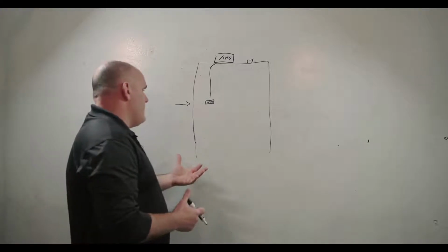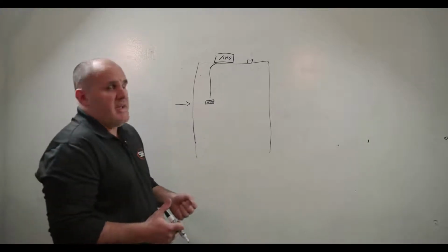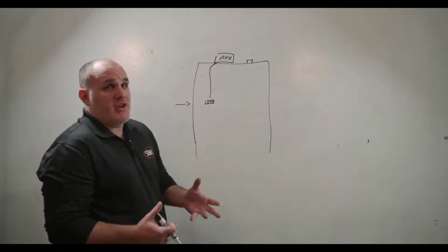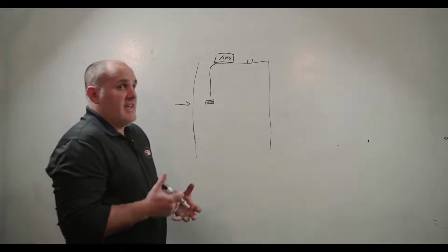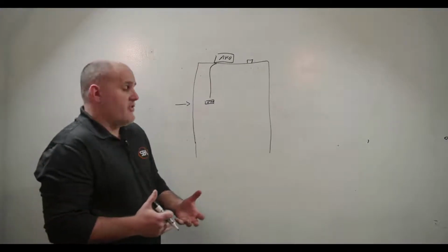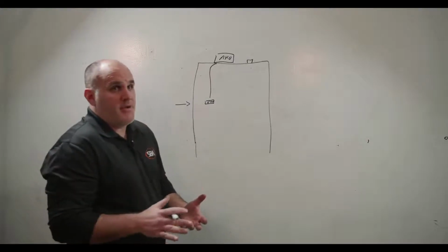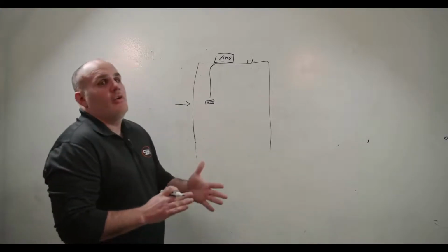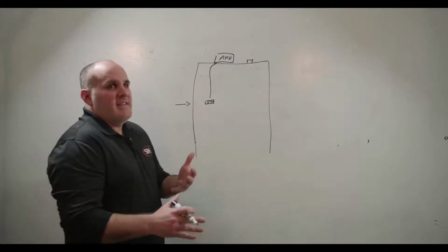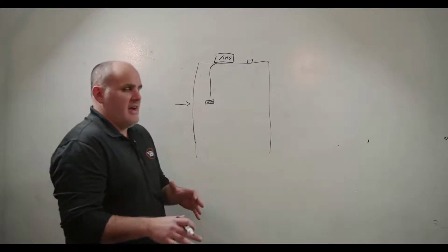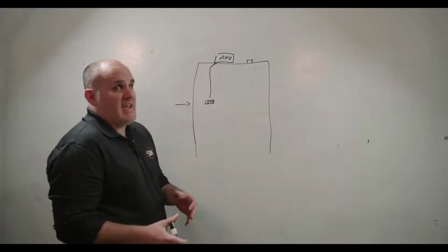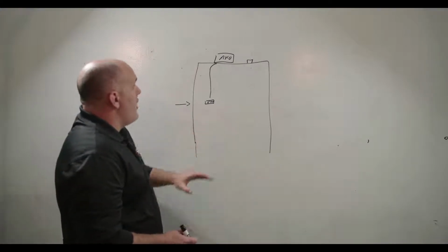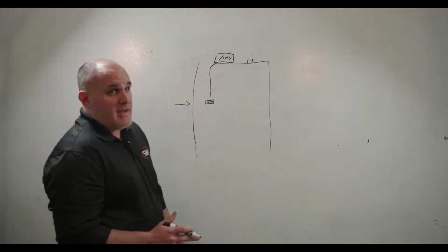Now, you've probably experienced high and low pressure buildings. You've walked into a building and it's difficult to open the doors. It makes kind of a sucking sound. You can feel the air being sucked through the door. That is a negatively pressured building. So one of the quick ways to tell if you're in a space that is negatively pressured is to put a piece of paper against the door and see if that paper gets pulled through the crack or if it gets blown away. And that can give you an idea real quickly, it's not scientific, if you're in a positive or negatively pressurized space.